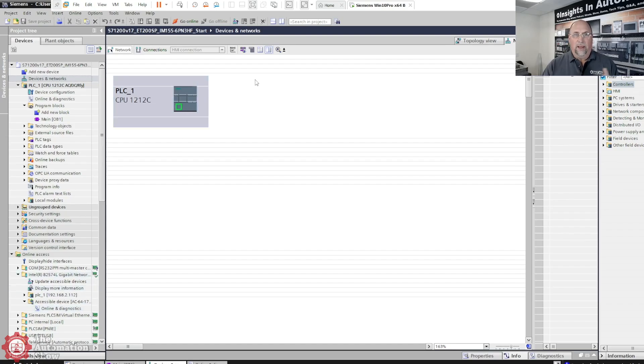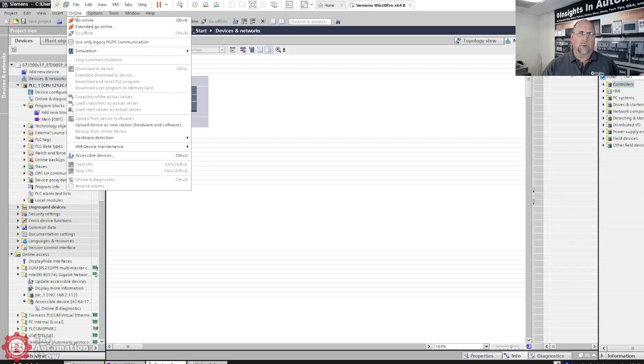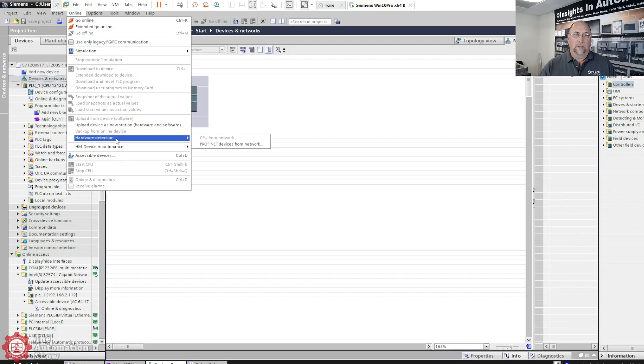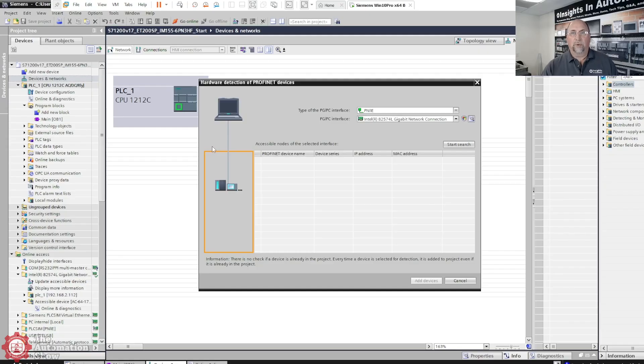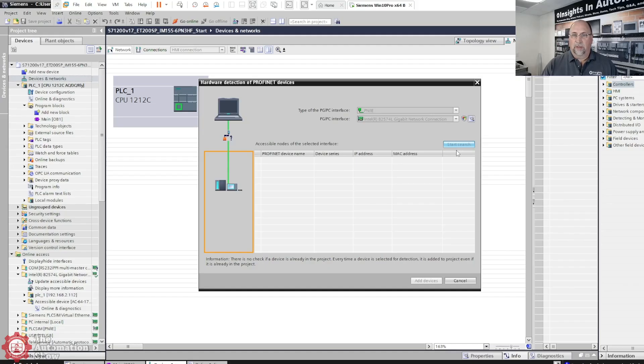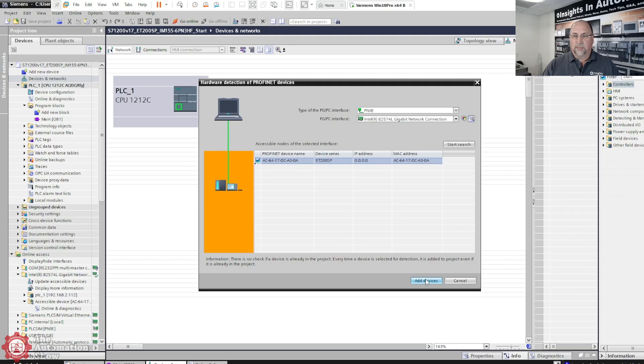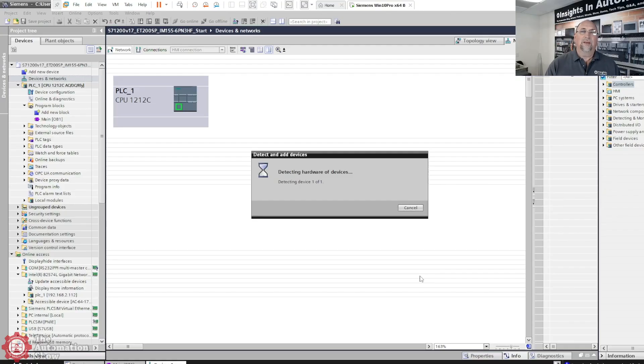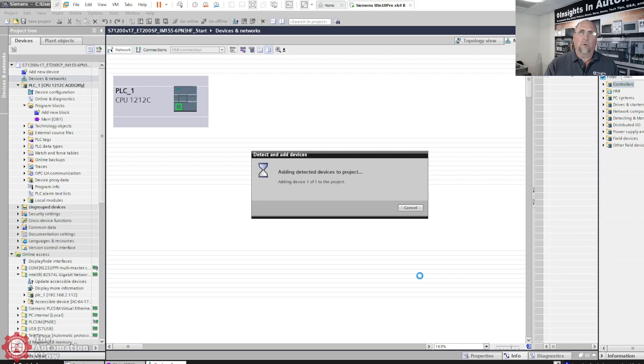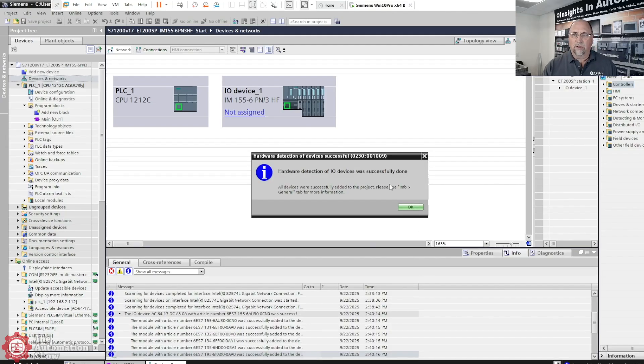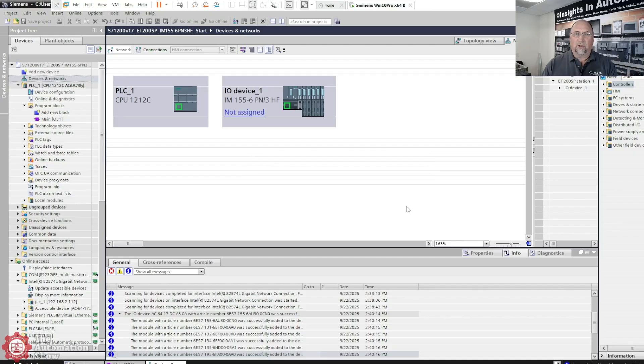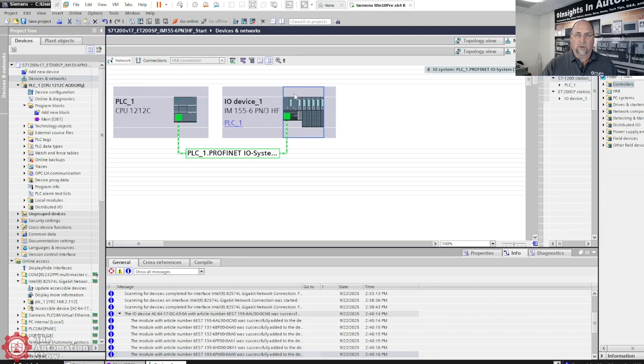Let's go back to our devices and networks in this project and add that existing unit in. I want to show you the easy way of doing this, which would be to go online and then go to hardware detection. Profinet devices from network, let's see what we get. I'll do the start search. The device out there, that ET 200 unit, does not have an IP address. I reset it to factory defaults. You can see it right there. Let me go ahead and add this into my project. The cool thing about this is it's going to add all the IO modules.